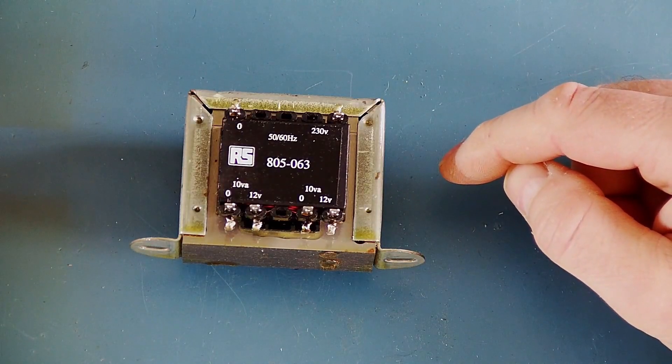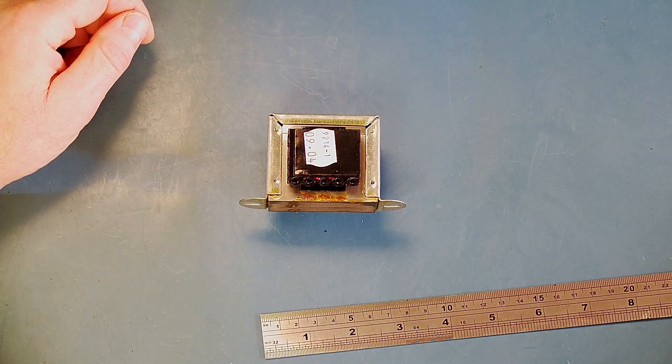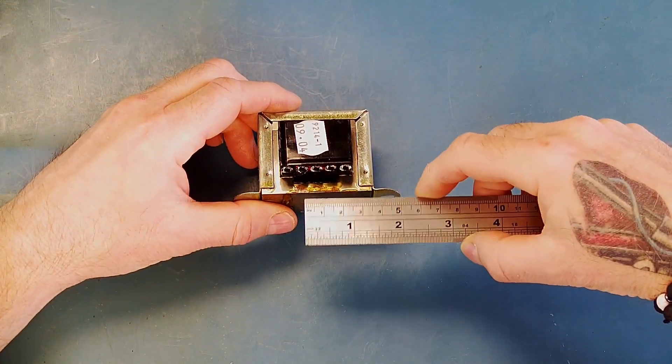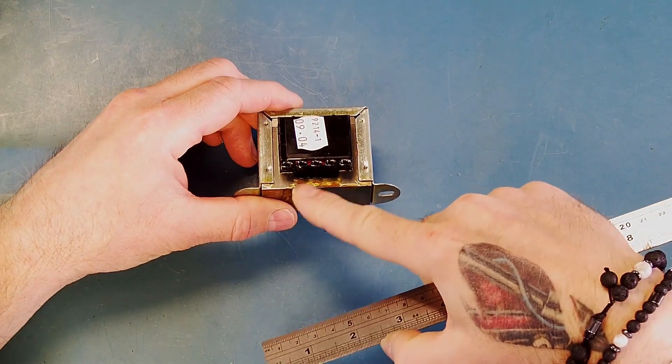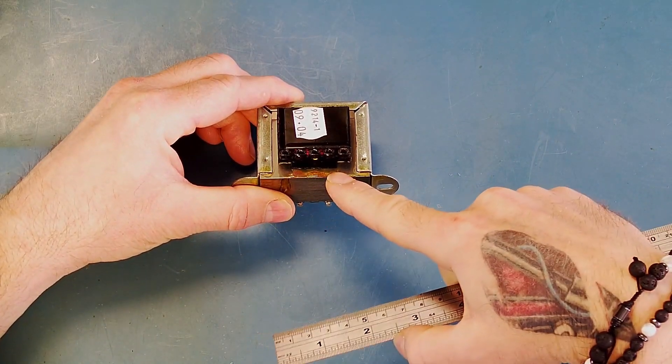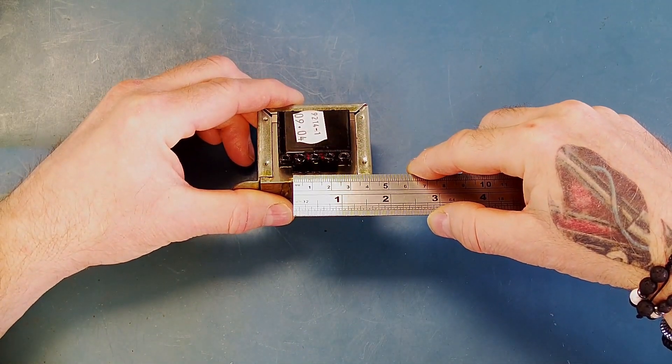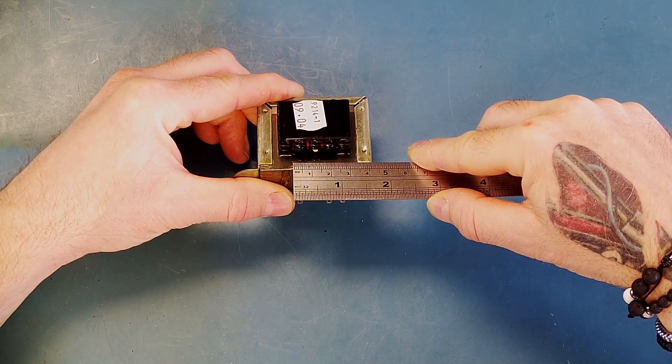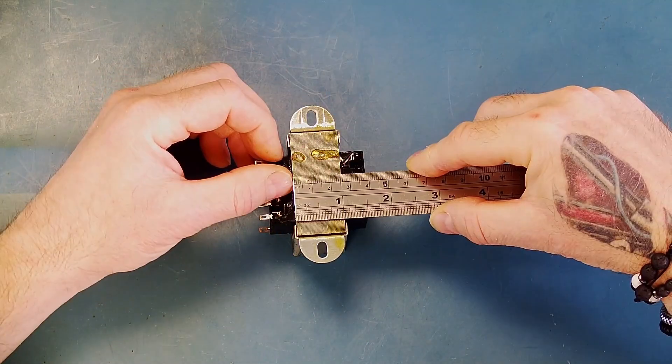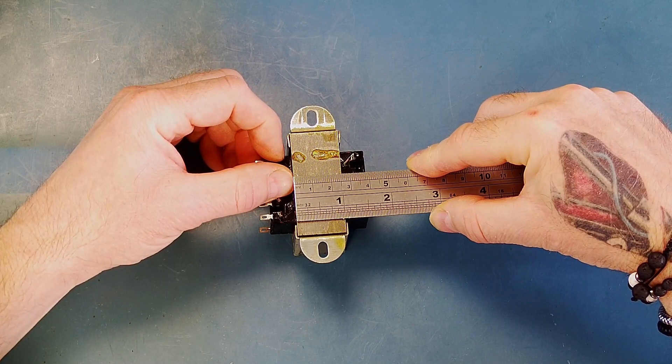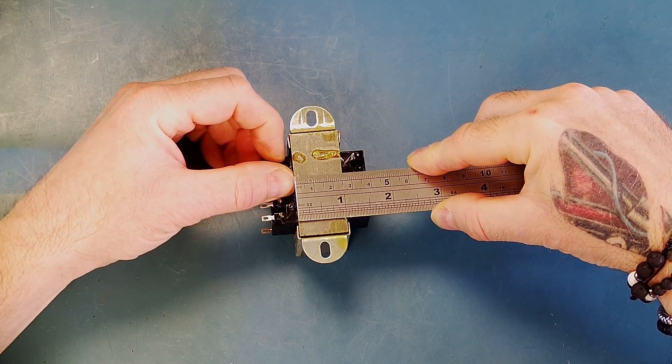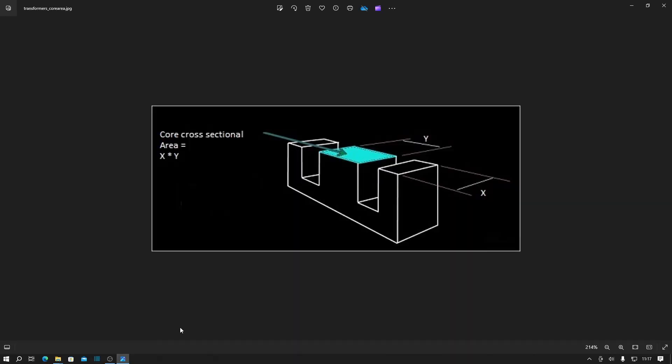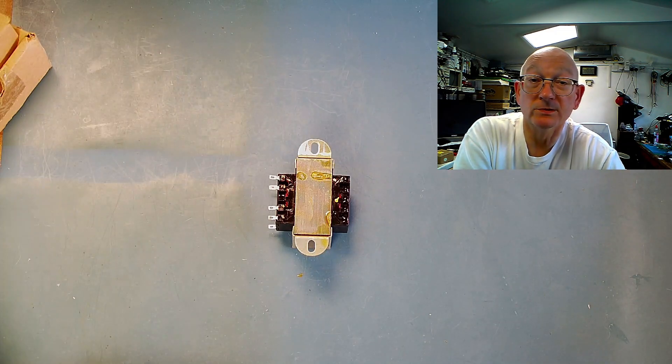As we said, we need to figure out the cross-sectional area of the core inside the transformer. If we measure this transformer what we need to do is to get an approximation of the length of the tongue sticking out here on the transformer. We can see that this one is approximately 23 millimeters. We measure across the stack of the laminations and that's approximately 25 millimeters. The two dimensions we've just measured are the Y dimension here which we measured at 23 millimeters and the X direction which is the height of the stack of the laminations we measured at 25 millimeters.